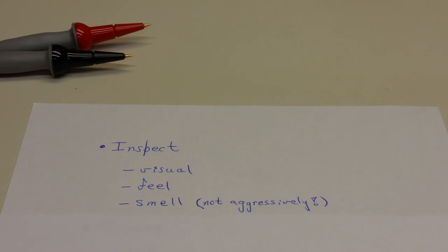The first thing to do is to inspect the equipment that you got and that you're about to use or repair in a fair amount of detail using your different senses. You need to look for cracked or rotted wires. You need to look for the suitability of the power cord. You need to be aware of uneven or bad or broken solder joints, signs of past repairs that could suggest problems that were repaired incorrectly, or just bad repairs in general.